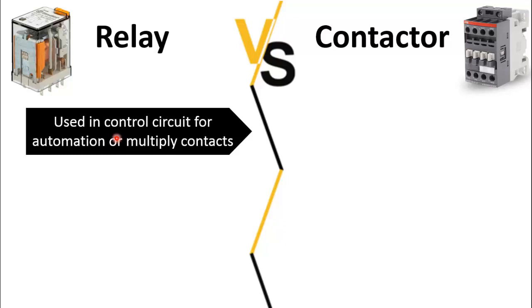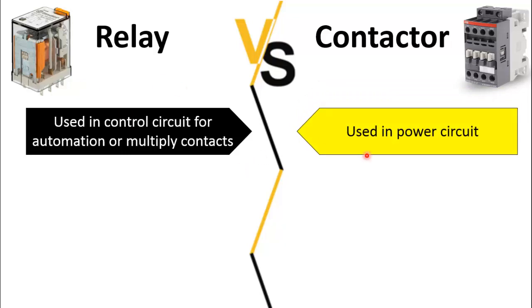A relay is used in control circuits for automation and also to multiply the contacts — you can have multiple normally closed and normally open auxiliary contacts in a relay. In order to use it in control logic or to multiply the contacts, you can use a relay. Whereas a contactor is used in a power circuit to switch a heavy load.